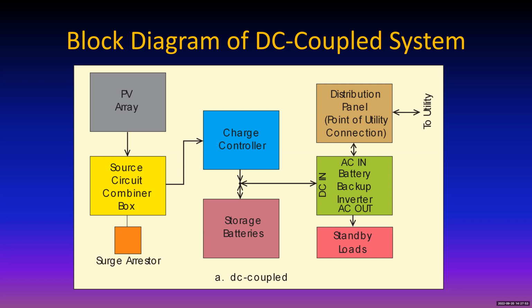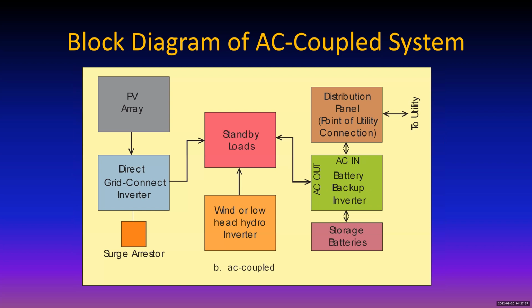All right, the other kind of system that's also very popular these days is the AC coupled system. What this one does is the DC from the array goes directly to a direct grid connect inverter, which means this inverter meets UL 1741. These are current sources, and they feed the standby loads directly at an efficiency of somewhere near 98%. If you have a little bit of loss in the wiring, then you're looking maybe a little below 98%, but those wiring losses are going to be there whether it's AC coupled or DC coupled. So your standby loads are powered up immediately, and any leftover electricity is then fed to the battery backup inverter.